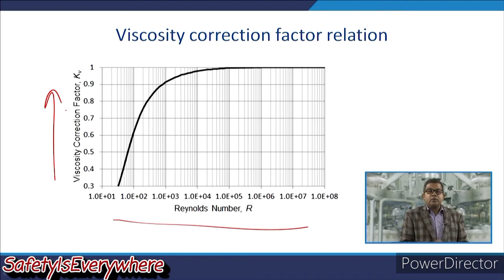Then we can go for the sizing for gas relief. This is for the conventional spring operated relief valve in gas or vapor service. So, choke flow through the orifice is assumed, which can be determined by this equation. Remember, we have already discussed this choke flow in the previous modules. Now, this is defined as W is equal to Kd A P1 square root of gamma Gc M upon Rg T into 2 upon gamma plus 1 to the power gamma plus 1 upon gamma minus 1.